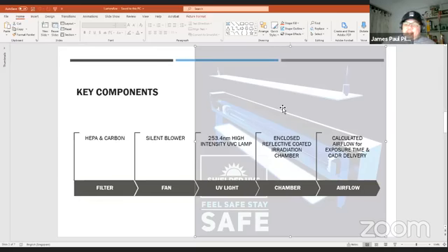So anything you need to add on this, Sheldon? Yeah, I just want to add that aside from the fan, the blower itself, we really need to think about the static pressure that can bring velocity and pass through the static loss of the filter.